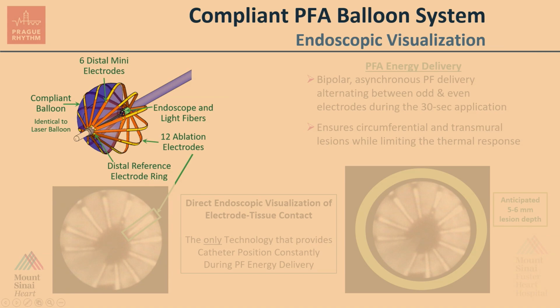If we look at each spline, there are a couple of important points. This orange region, this is the electrode, the ablative part of the electrode. You can see it extends from the most distal aspect to this one point. There's also a small mini electrode shown here, and that mini electrode is important. Oh, I'm sorry, I said it wrong actually. The electrode is actually the yellow part from here all the way to the major part of this. There's also these mini electrodes that you can record electrograms. So there's 12 splines for ablation, and every other electrode has a mini electrode for recording electrograms. So you can, for example, measure electrograms inside. You can pace from there if you want, et cetera.